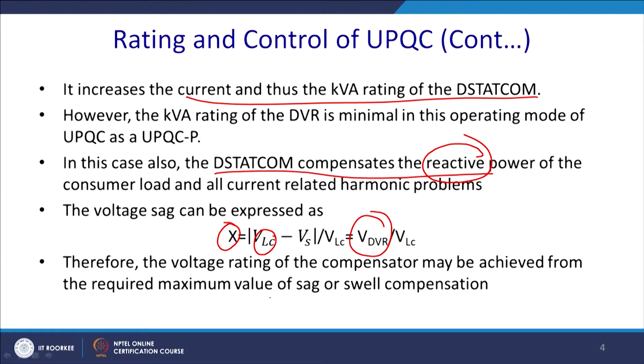Therefore, the voltage rating of the compensator may be achieved from the required maximum value of the sag and swell compensation. Thus, what will be the rating in case of the UPQC-P? UPQC-P mode of operation requires minimum injection of voltage and thus minimum VA rating for DVR, but the D-STATCOM will pay the cost for it, at the expense of the D-STATCOM rating, which increases due to the large flow of active power through the D-STATCOM. Therefore, this type of UPQC does not have a minimum value of VA rating, and it consists of both the elements of the UPQC.